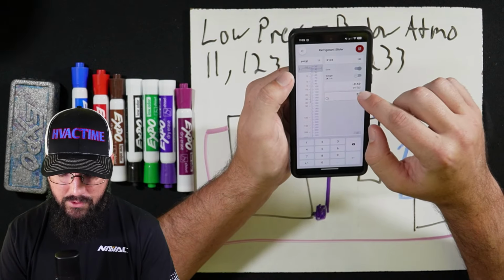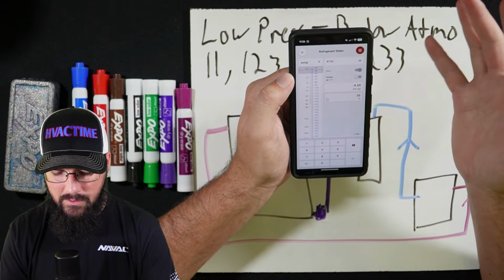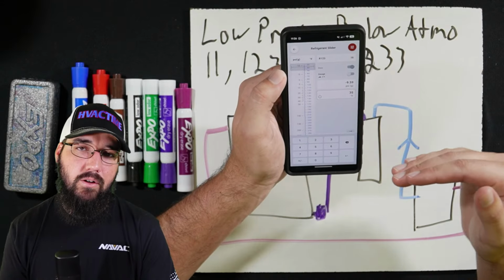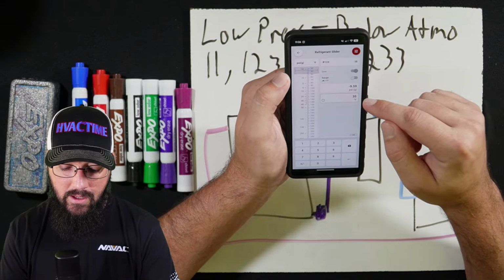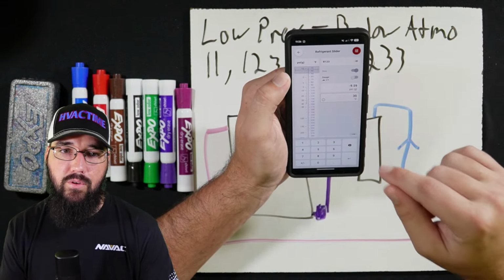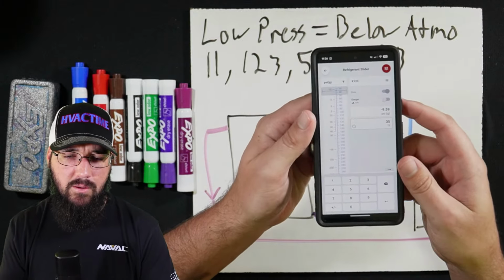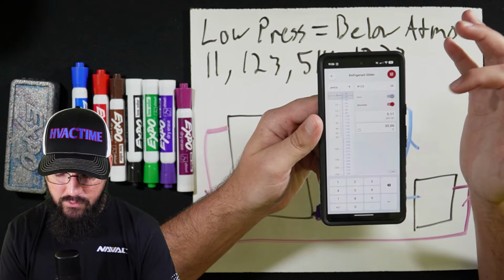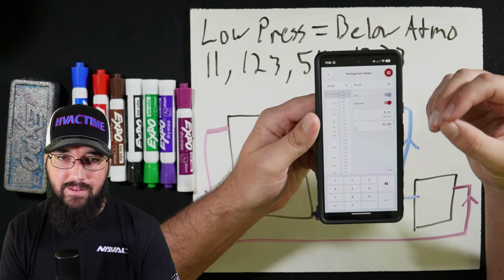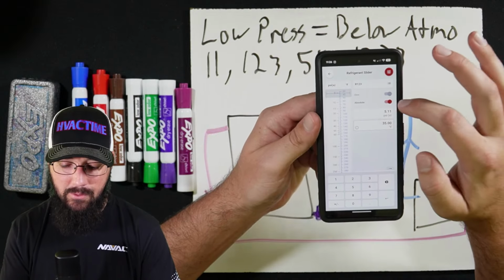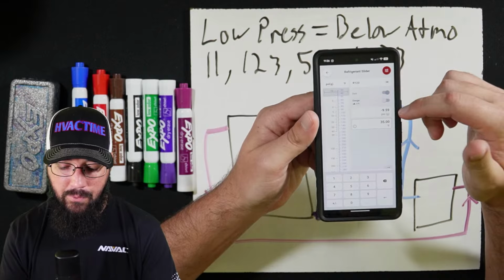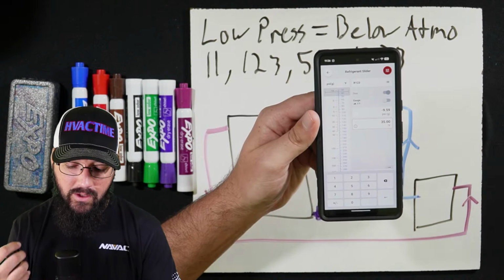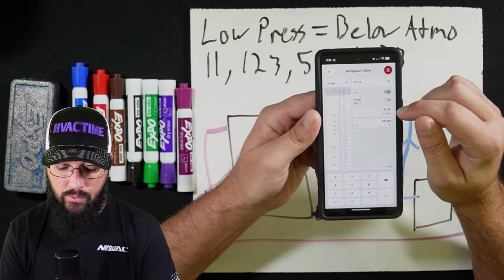Now this is in gauge. So my gauge pressure would need to read basically negative 10 psi. So from 500 microns to negative 10 psi, I have now crossed over 35 degrees of saturation for this refrigerant. I don't know if you can see that, but if we're going off of absolute, then it would be 5 psi A, not G. That's absolute pressure, but most of the time we're operating in a psi G context, or at least I do.